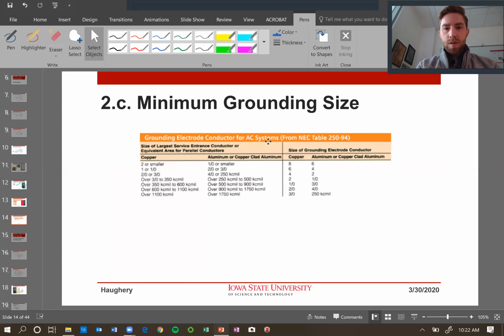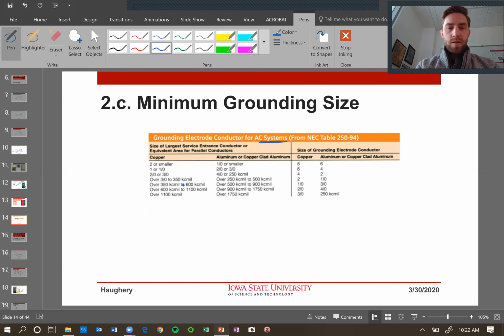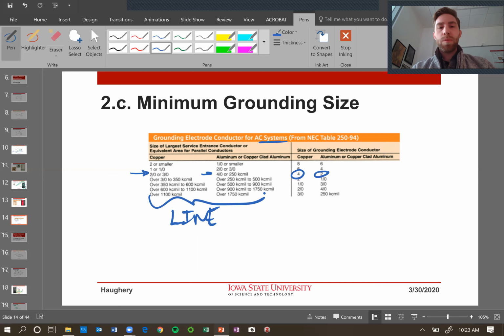And then if we have our system grounding, and we have a size of the largest service entrance cable conductor, so the lines, the hot wires, if we look at those, and we have a 2-aught or 3-aught, then we're going to have a copper 4 conductor. If we have an aluminum 4-aught, then we're going to have aluminum grounding of 2-aught or 2 gauge. So you go based off of the line size, whether copper or aluminum, and then here is the grounding. And usually GND ground is the conductor that we would use.